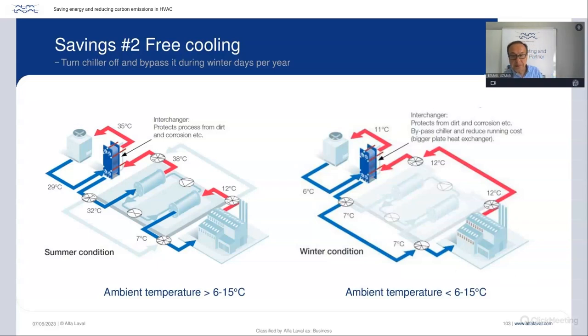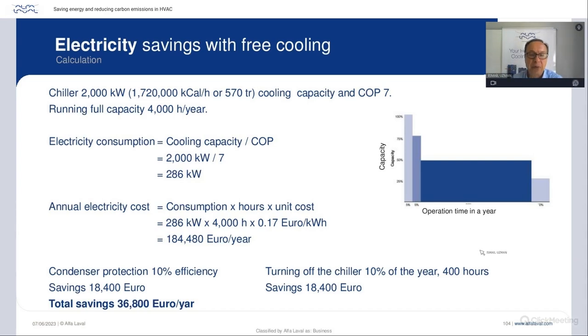Now, when it comes to the savings, we have a rule of thumb that we use, and we assume, for example, a COP of 7 on average for water-cooled chillers. And in this example, if we have a chiller which is 2,000 kilowatt with a COP of 7 running half the year, 4,000 hours per year, this is a typical illustration of the savings that you can make with this 2,000 kilowatt chiller cooling capacity. We basically divide the cooling capacity by the COP, so it's 2,000 divided by 7, and this is the electricity that's used to run this chiller.